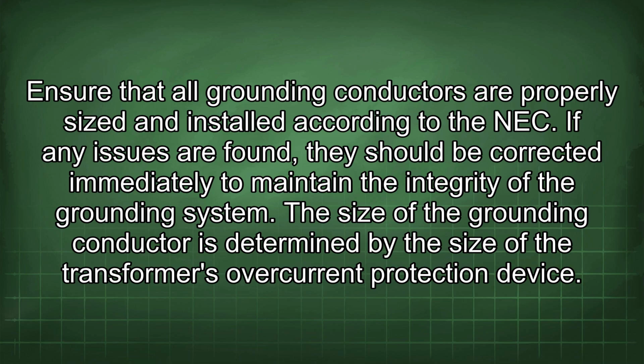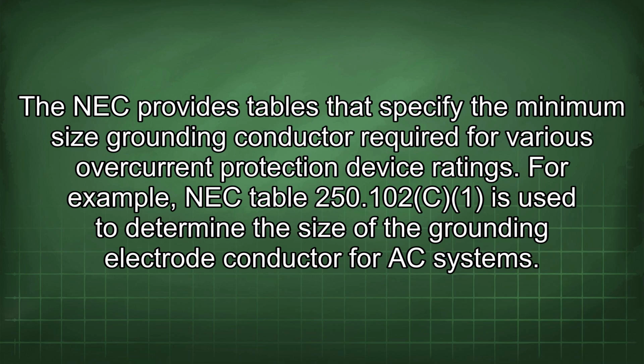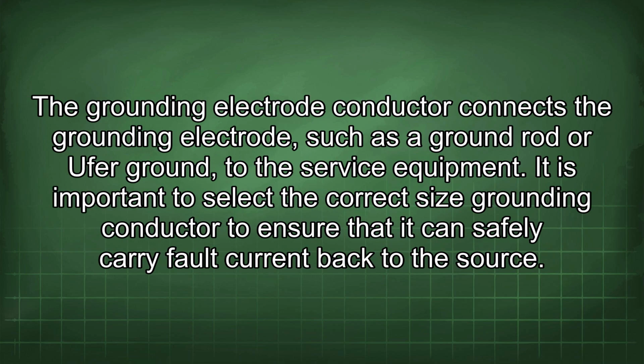The size of the grounding conductor is determined by the size of the transformer's overcurrent protection device. The NEC provides tables that specify the minimum size grounding conductor required for various overcurrent protection device ratings. For example, NEC Table 250.102 is used to determine the size of the grounding electrode conductor for AC systems. The grounding electrode conductor connects the grounding electrode, such as a ground rod or UFER ground, to the service equipment.